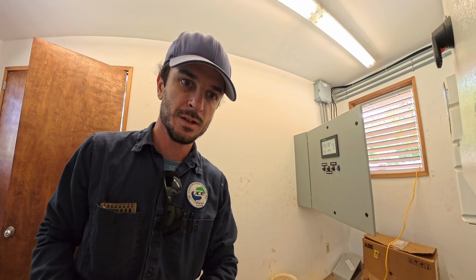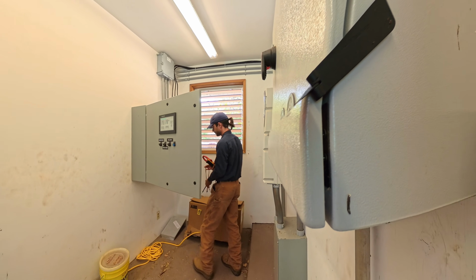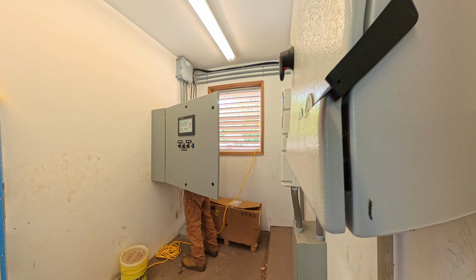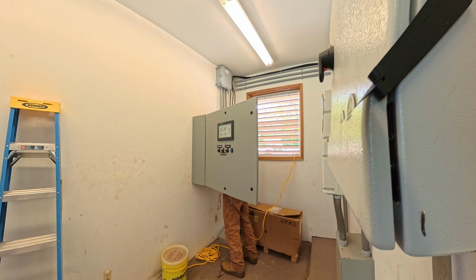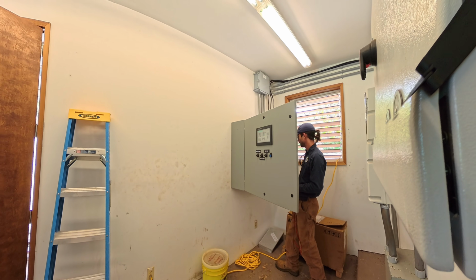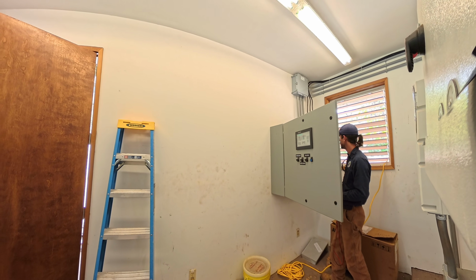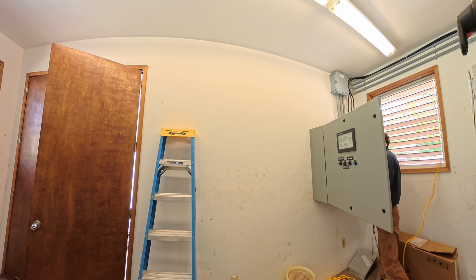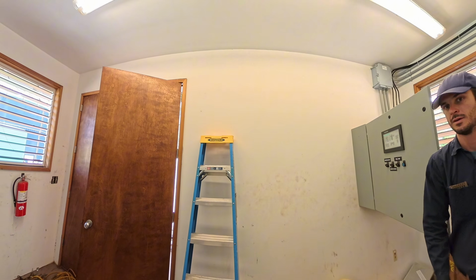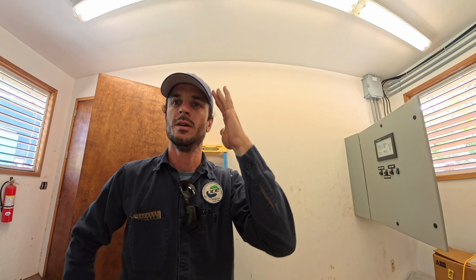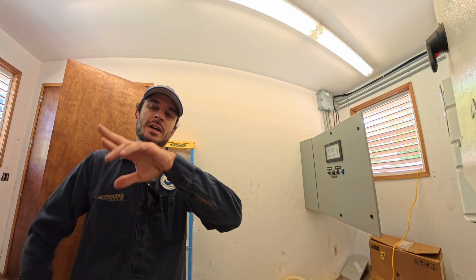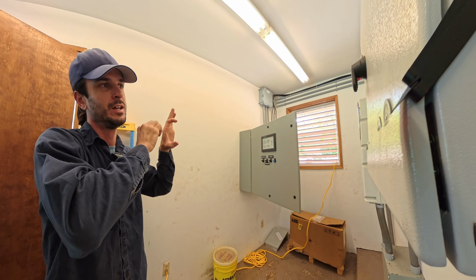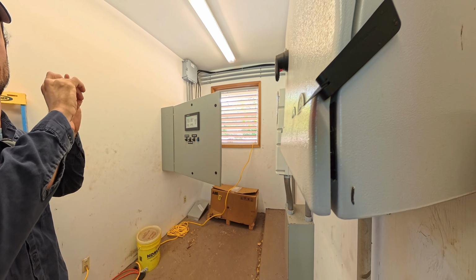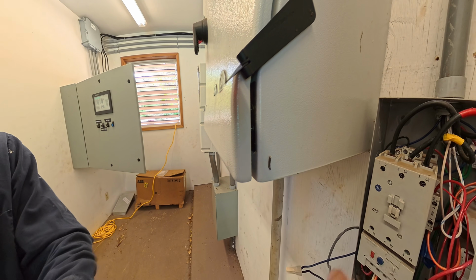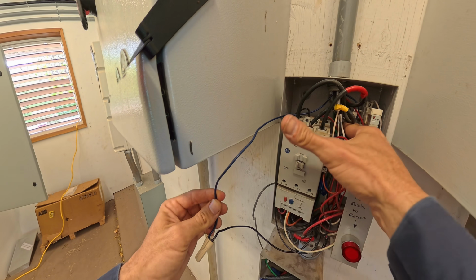Let's just see where our voltage is. Where is that coming from? I think it's coming from over here, honestly. So now it's a 120 relay output over there on our PLC, and it's a question of where that's the beginning of our run. There is going to be 120, and it's going to go essentially through the PLC relay output. And the source for that 120, I believe, is inside of here. We've got this blue and this blue.